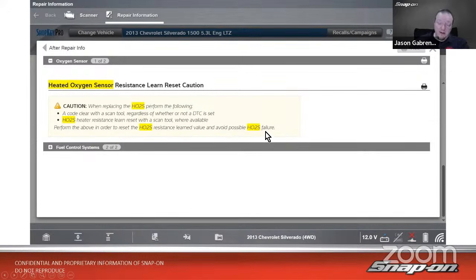Over time, it's going to learn that the resistance in the heater circuit has increased, so it needs to increase the amount of current flow or the pulse width on the heater control circuit in order to keep it heated up the same. If you put a brand new sensor in there expecting to see a much lower current than it's getting, and it's getting fed that high current because you haven't reset it, you will burn out that element pretty quick because it's not prepared for it.